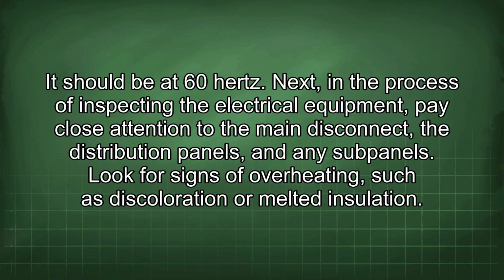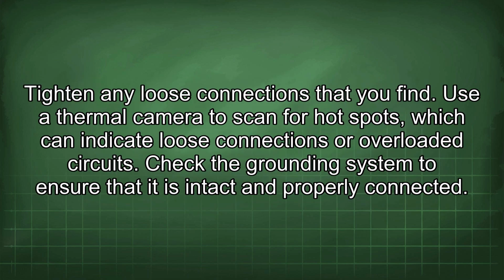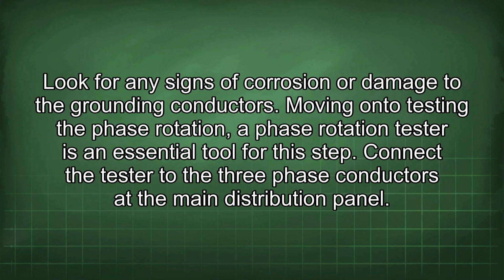Next, in the process of inspecting the electrical equipment, pay close attention to the main disconnect, the distribution panels, and any subpanels. Look for signs of overheating, such as discoloration or melted insulation. Tighten any loose connections that you find. Use a thermal camera to scan for hot spots, which can indicate loose connections or overloaded circuits. Check the grounding system to ensure that it is intact and properly connected. Look for any signs of corrosion or damage to the grounding conductors.